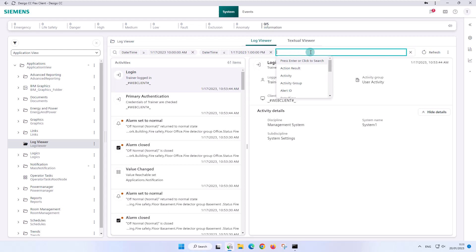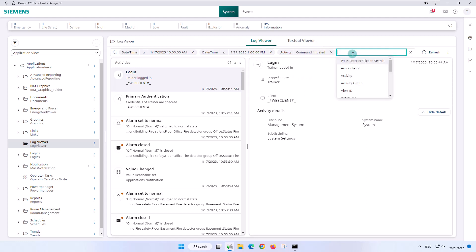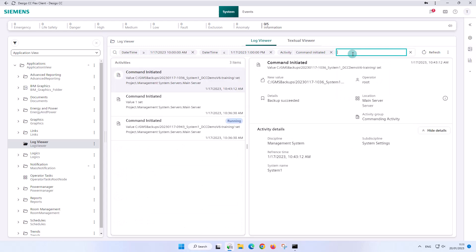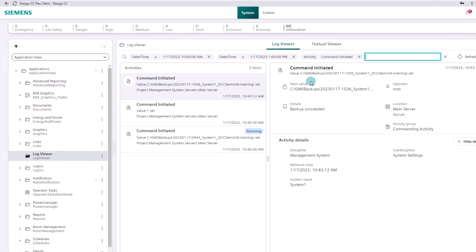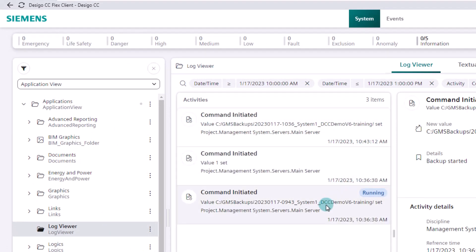We add a filter that should help us to find the exact time and the operator who performed set point changes in a ventilation system. The activity we are looking for is called command initiated. With this attribute we can find most of the command executions in the system. The search result is three log entries, but not really what we expected.